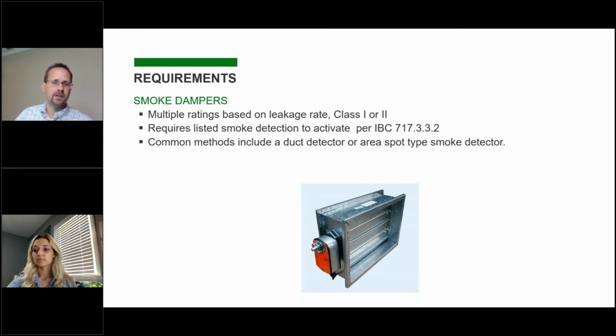So smoke dampers, there's a lot of different ratings. The code allows class 1 or class 2. We're going to talk more about this later, so I'm not going to spend a lot of time on this slide. But it obviously needs a smoke detector. There are multiple options on how that can be applied to close the damper upon detection of smoke. And it needs to be coordinated with your HVAC system as well.